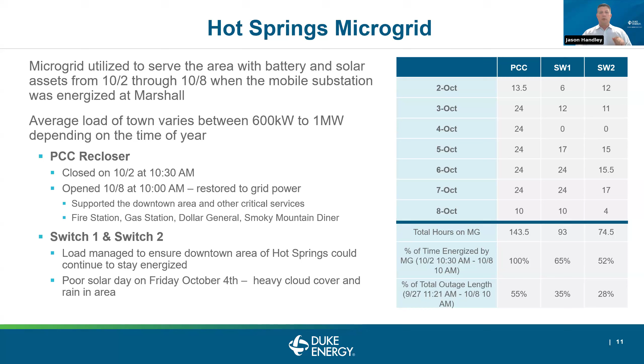Some key takeaways for the system: switching plans are critical. Automation and automatic switching is always ideal, but you need a backup for when automation fails, or when power safety shutoffs, similar to the Helene response, are called into play. We couldn't have automated control going from grid power to microgrid power; we had to do it through manual operations, with a set of switching steps we had to go through with our distribution control center. Make sure you've planned these out extremely well.